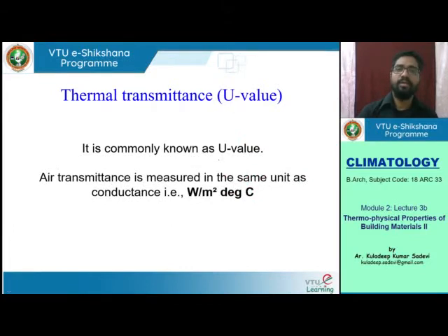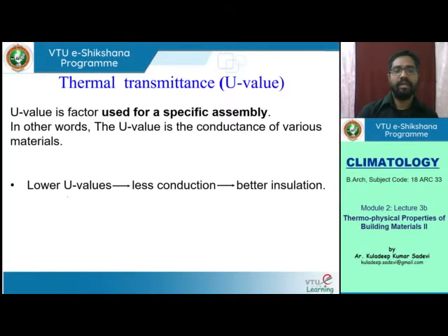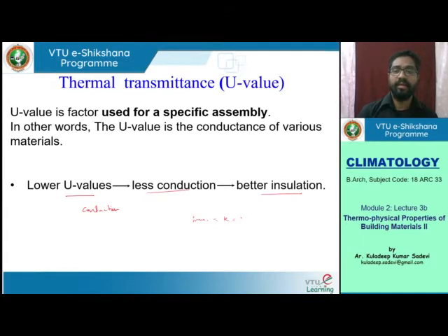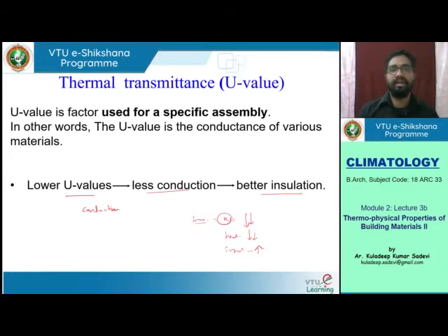The units of conductance and transmittance are the same because transmittance is conductance including surface conductance. If the U value is lower, conductance is lower, meaning less heat flow — which means better insulation. For insulating materials, the K value (conductivity) is very low, meaning heat flow is also very low, giving high insulation. Since conductance is proportionate to conductivity, lower U values offer good resistance. U value is most commonly used and is known as the overall coefficient of heat transfer.